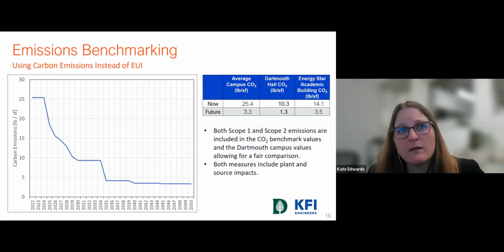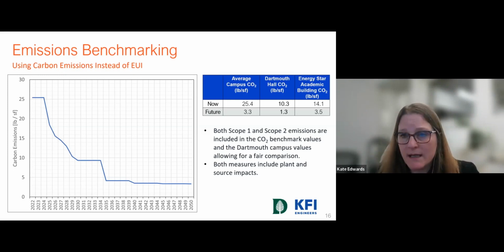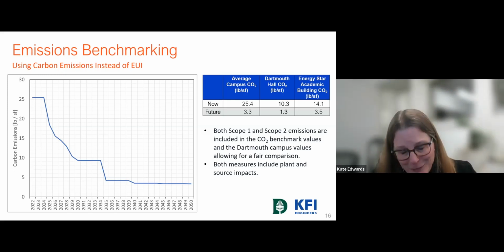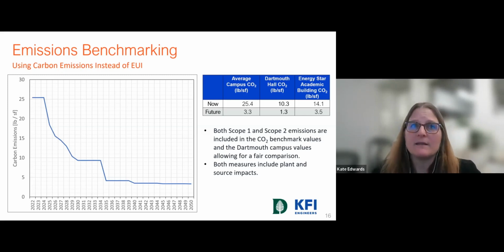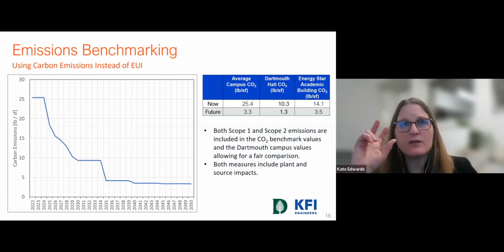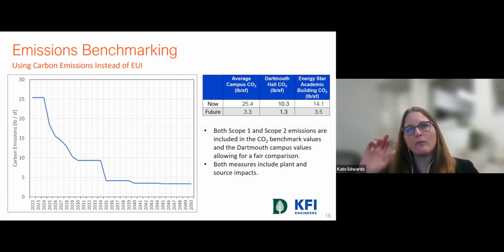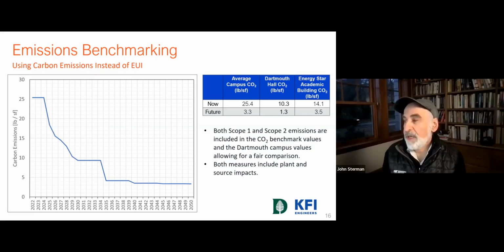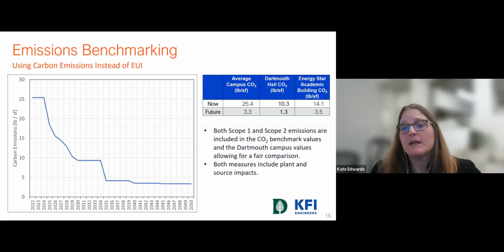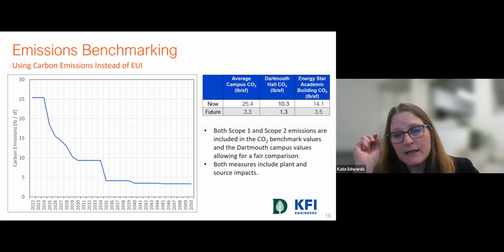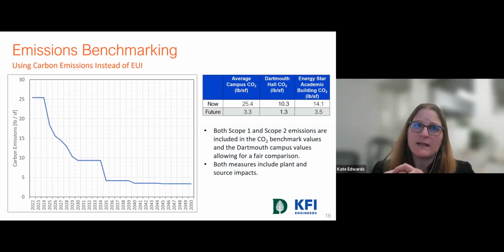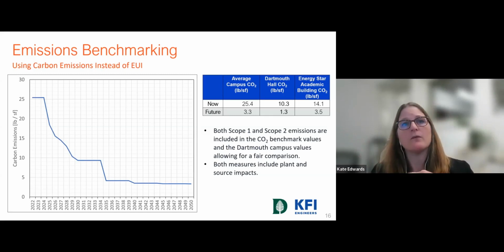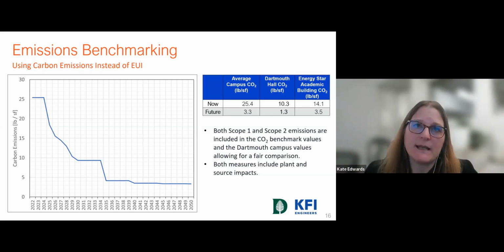Energy Star publishes benchmarking data based on the CBECS data, the Commercial Building Energy Consumption Survey, which looks at the existing stock of buildings, and you can tailor that to your zip code. They adjust it for your heating degree days, basically. One limitation, though, is that the Energy Star database does not include all building types, especially laboratory and science building types.